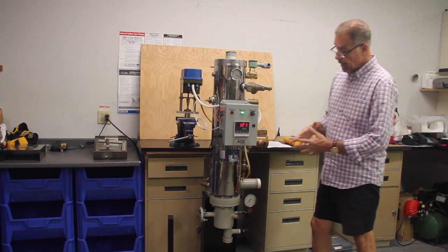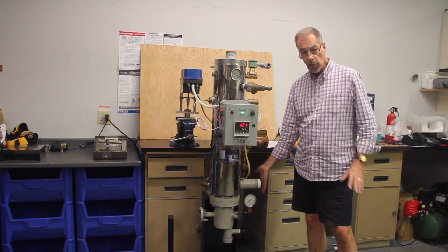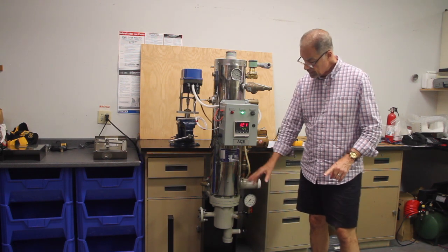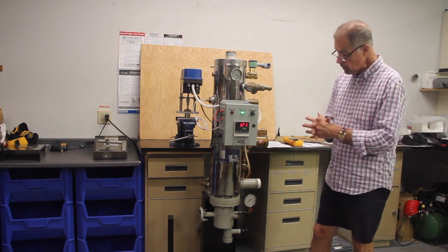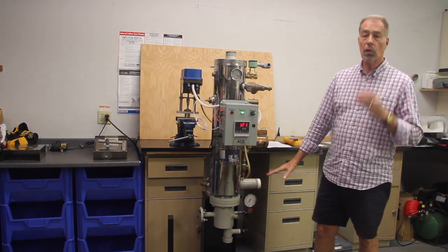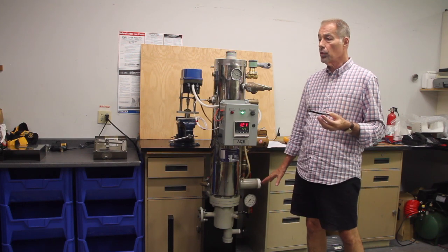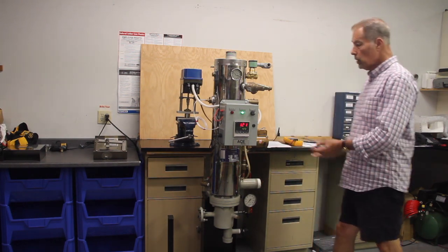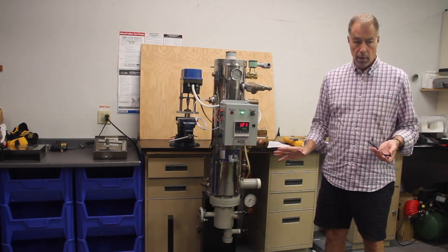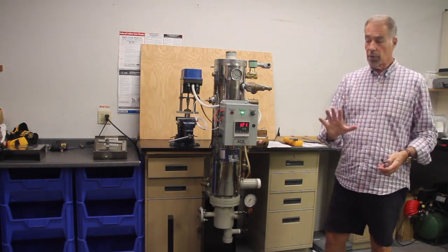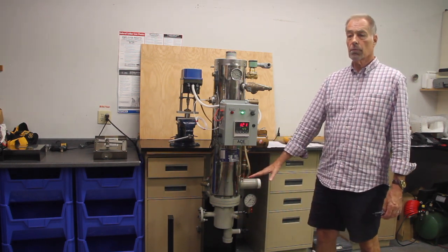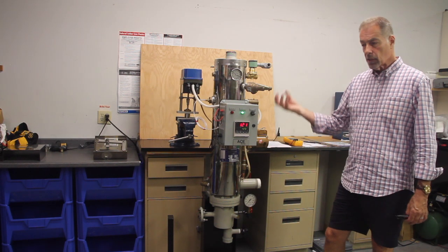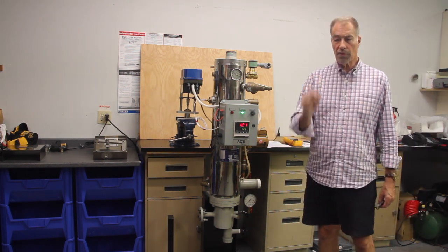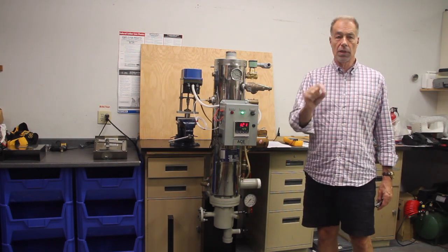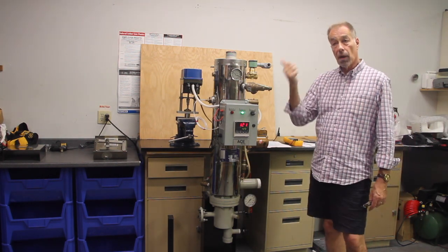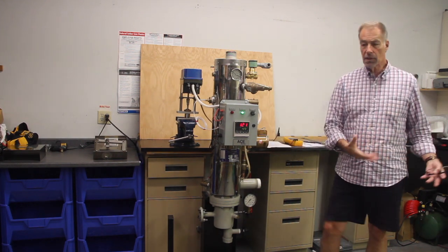So we know that as long as your incoming cold water is 100 degrees or less, we can condense the steam to condensate and deliver condensate that is well below the normal temperature, which is 200 plus degrees, going into a trap, flashing into a condensate receiver. It's very energy inefficient. So what we provide for you, Colby, and for other customers is steam comes into this unit, but it comes out as a condensed, subcooled condensate. Subcooled is defined as any temperature below 190 degrees.